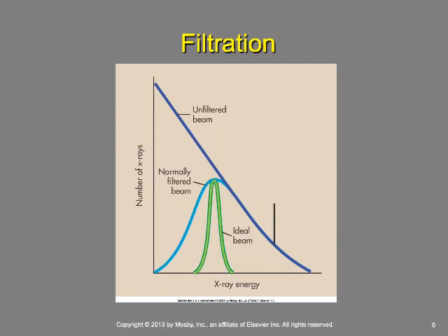If we do not filter our X-ray beams, though, because of the way that Bremsstrahlung works, the predominance of our X-rays would be very, very low energy. There would be a lot of X-rays that are very, very low energy, right? And so this would be roughly how our spectrum would look, with the addition of this little spike here for characteristic interactions. Okay? So again, not very helpful, because all of this stuff here is too low to even participate in photoelectric effect.